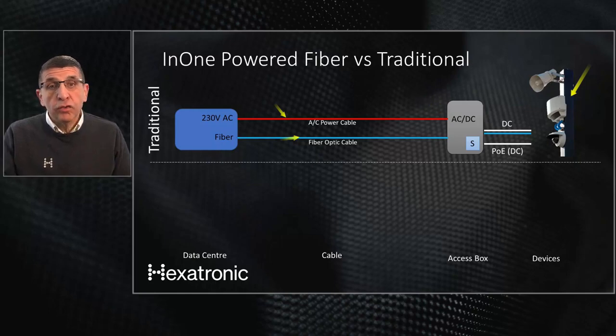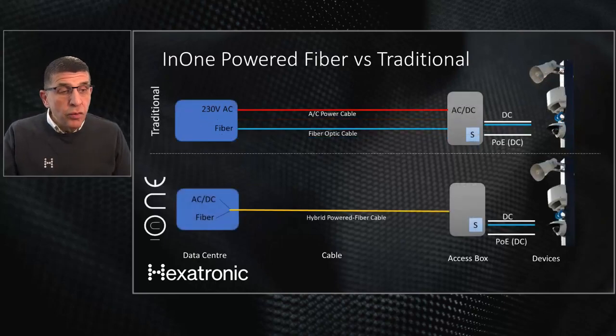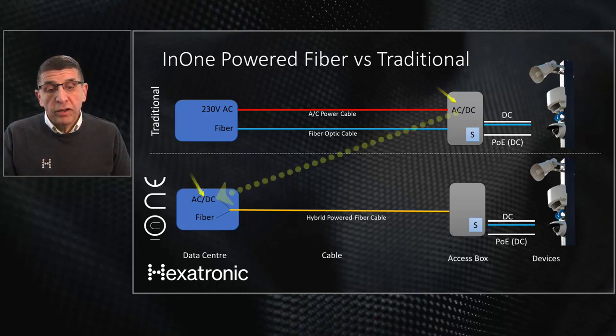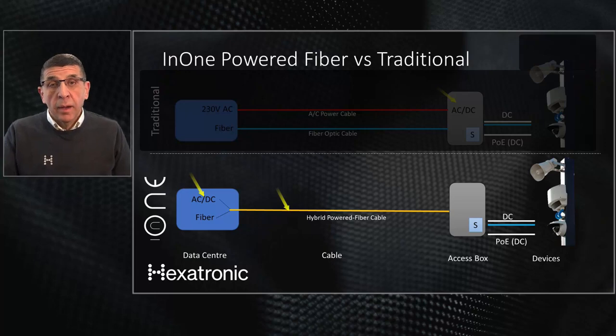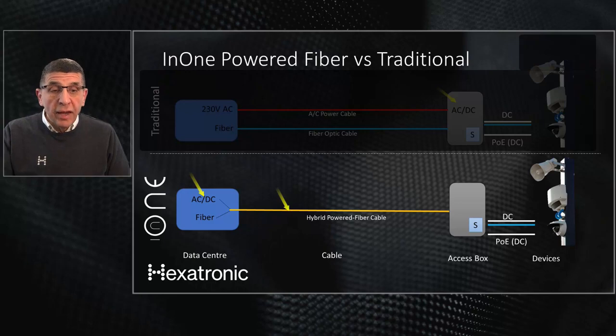So how have we solved this problem with the InOne solution? We have moved the AC-to-DC PSU to the central point. Now we have the AC-to-DC conversion here, which allows us to carry DC power and fiber optic in one hybrid cable out to the devices. This means we have gotten rid of the separate AC power cable infrastructure — a significant cost saving and much faster to implement.